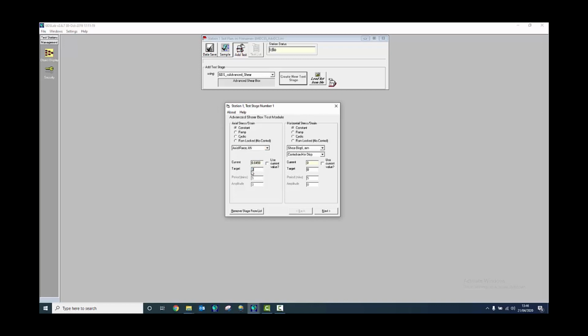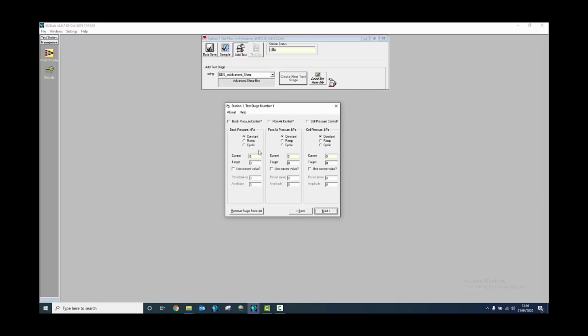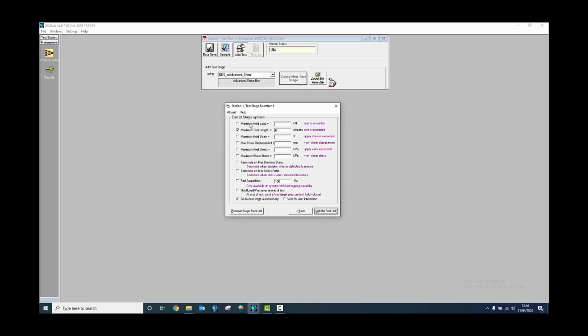For this test, increase the target to 2 kilonewtons, and we can hit next. Over here, we have a number of additional options depending on the system. For GDS Electromechanical Dynamic Cyclic Simple Shear, EMDCSS, those options are not applicable, so we can just click next. Then we can specify the end of the stage conditions and all of those parameters. For this test, we'll just wait for user interaction and we'll move to the next stage manually.